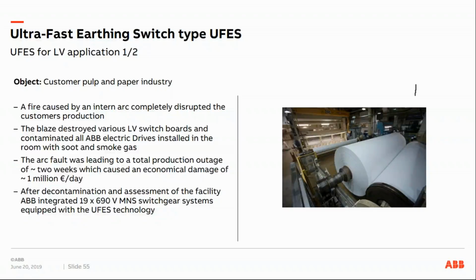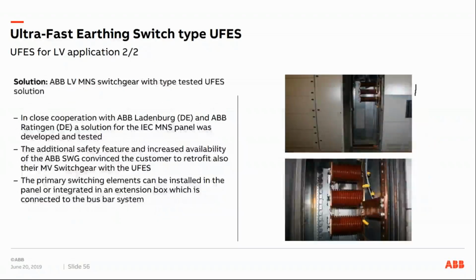Here again, a pulp and paper industry, where we have also a low voltage application due to an arc fault. The customer's switchgear system needed to be exchanged, and here we had 19 690 volt MNS switchgears by ABB equipped with the UFES technology. Here you can see it also installed in a service box kind of application, an extension box so to say, connected directly to the bus system.